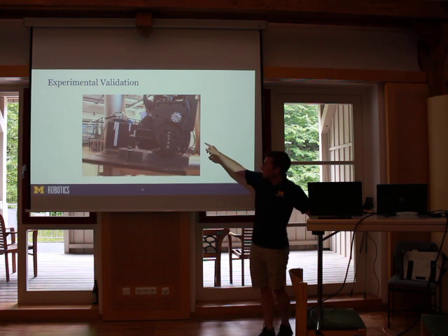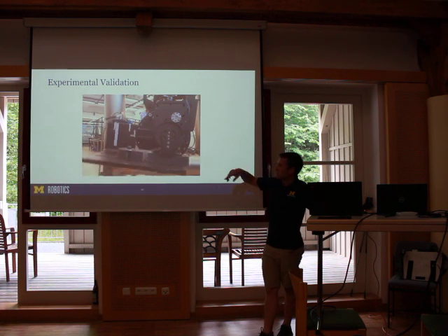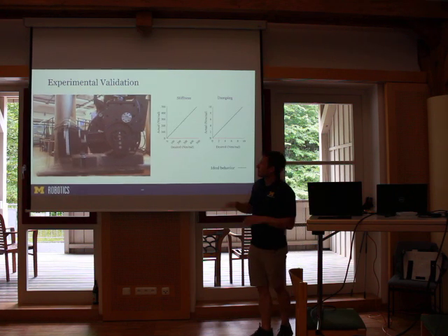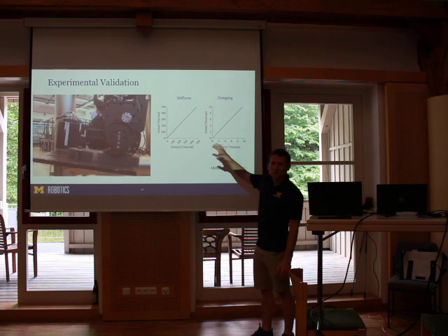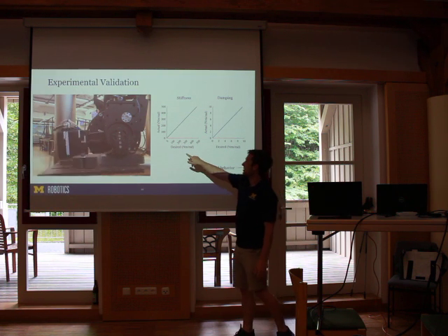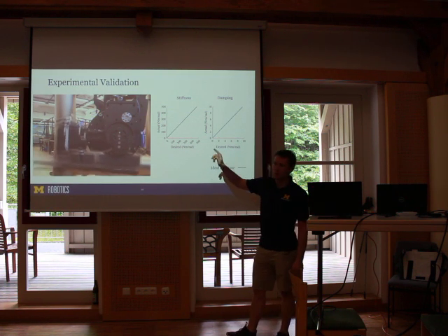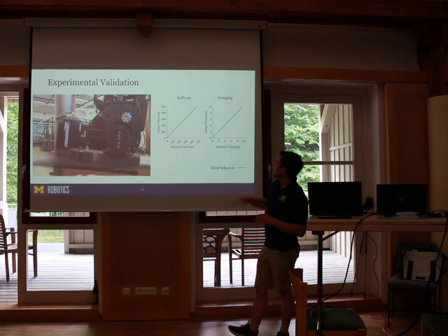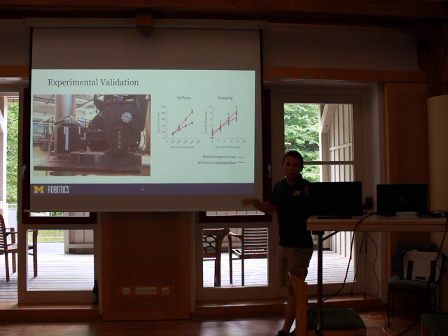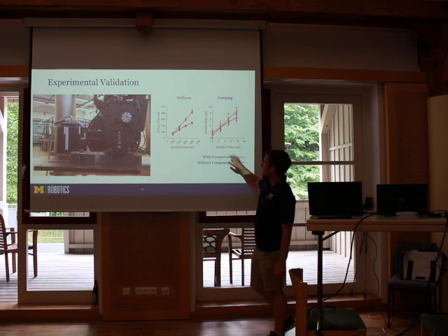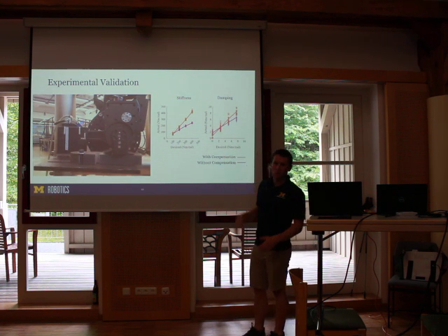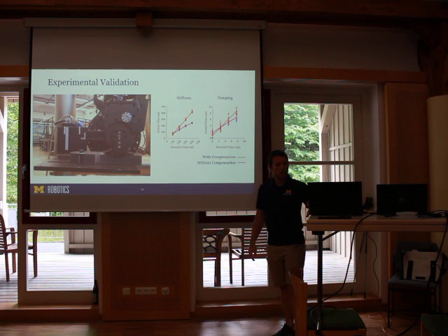So we stuck this to the ankle joint. We stuck it on a dynamometer, and we ran it through a bunch of chirp signals. We tried to have it render different stiffness and damping pairs. So on the x-axis here, you'll see the desireds, and then what we actually give when we regress the data on the y-axis. If we do it perfectly, it'll look like these lines. We're not perfect, but we're much better with our compensation strategy than if we ignored those dynamics altogether.